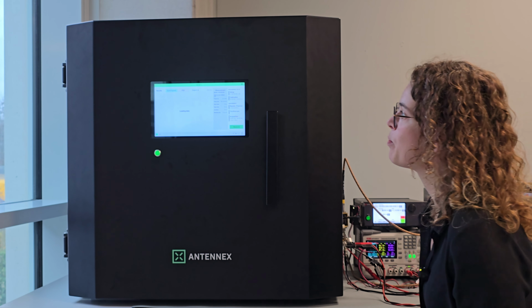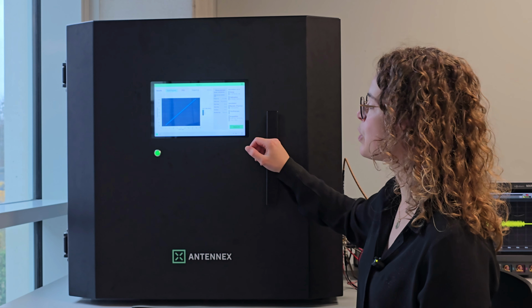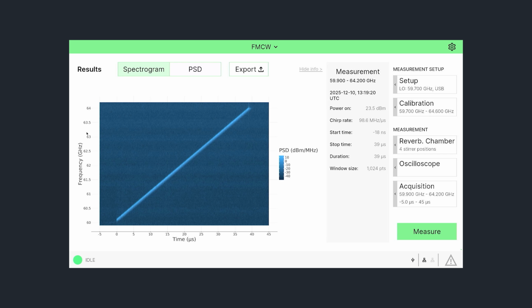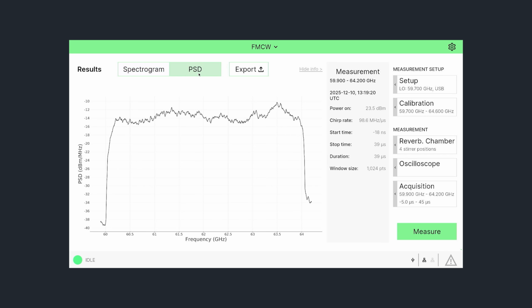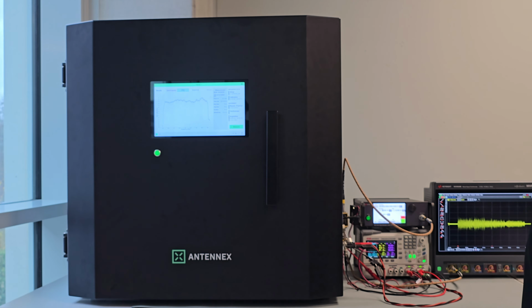And then in just a couple of seconds, you can see the results of your measurement. So first we will have a spectrogram. In the spectrogram, you can see that the chirp indeed covers a pulse of 40 microseconds, chirping from 60 to 64 gigahertz. From this, you can extract the linearity of your pulse, the chirp rate, the duration, and the total power that is being transmitted during the full chirp. And you can also go to the power spectral density, in which you see the power spectral density over frequency of the chirp. That's it.